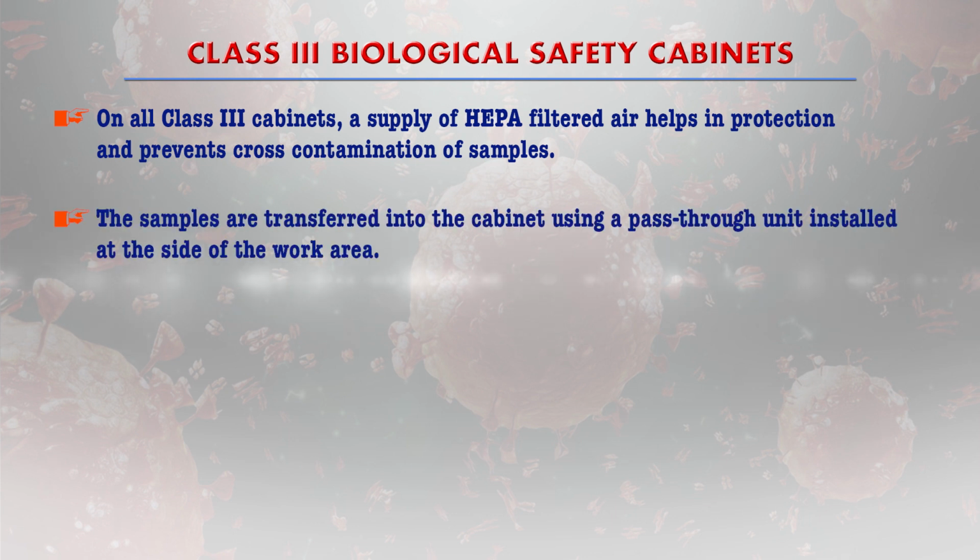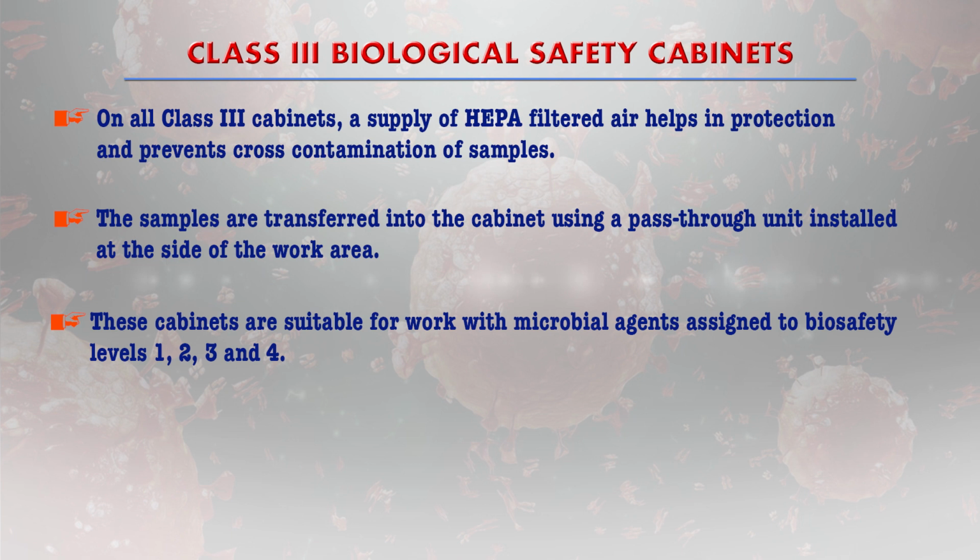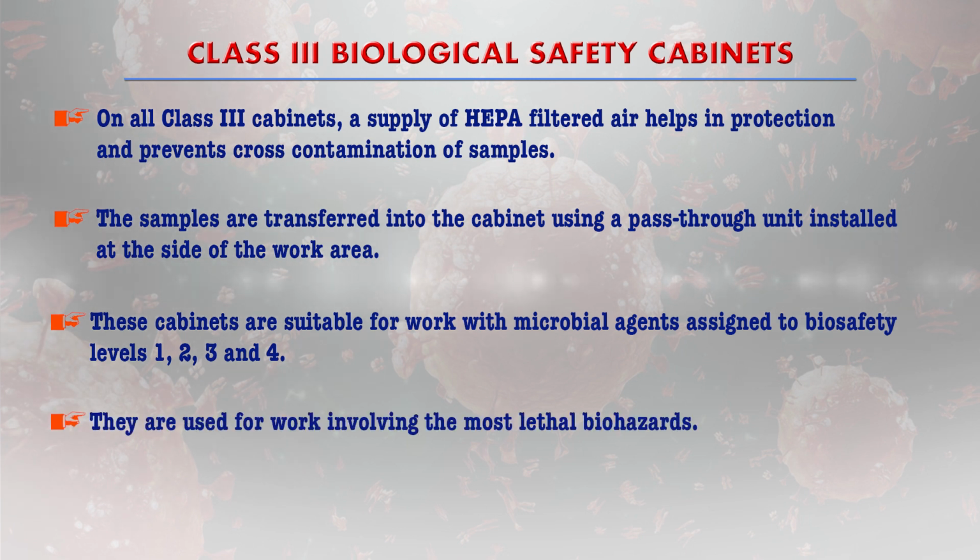Now the samples are transferred into the cabinet using a pass-through unit installed at the side of the work area, and these cabinets are suitable for all microbial agents up to biosafety level 4. They are usually used for the most lethal biological organisms or lethal biohazardous materials, providing the utmost safety to the worker and the scientist who is handling these organisms.